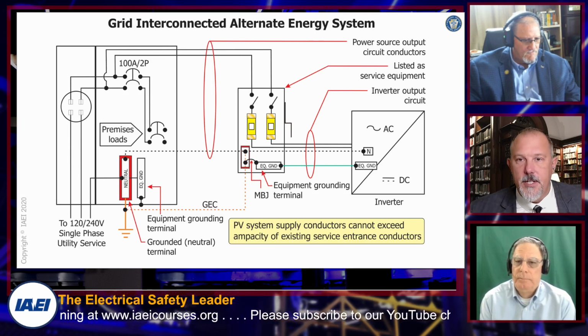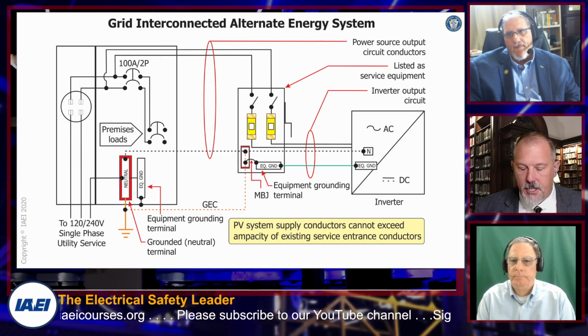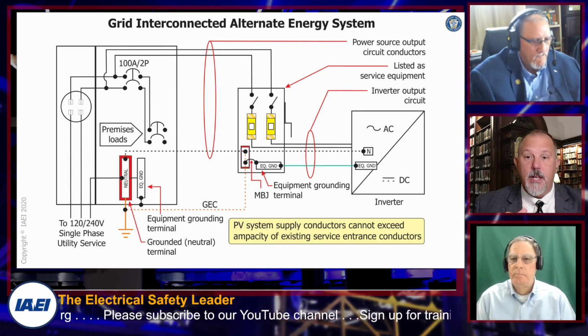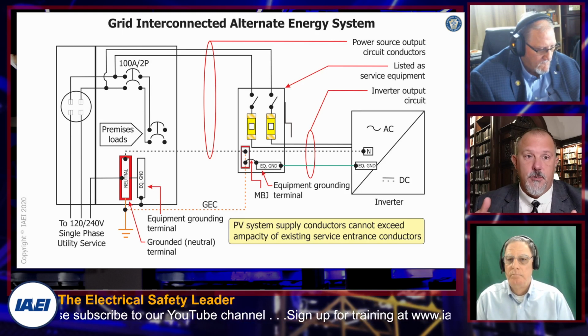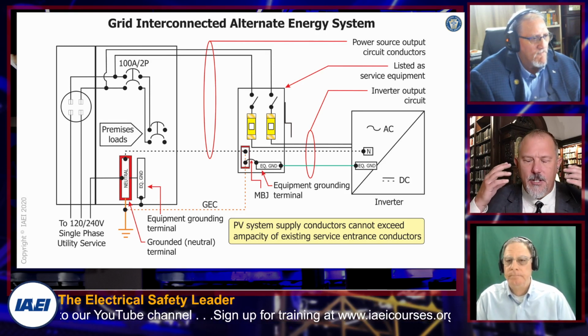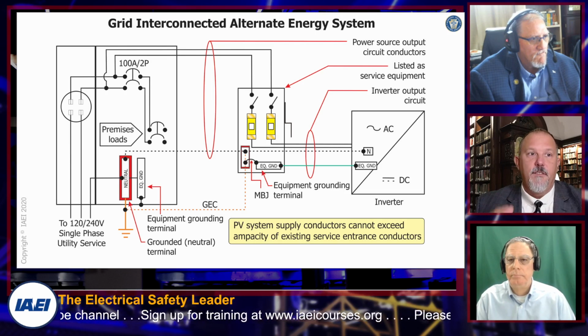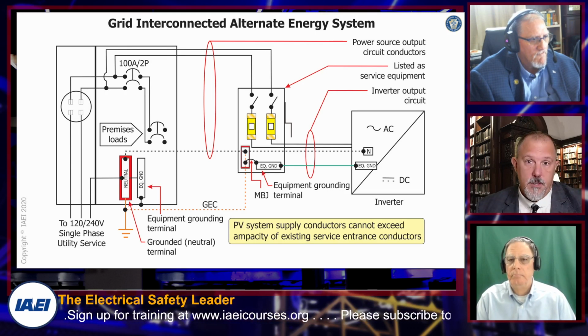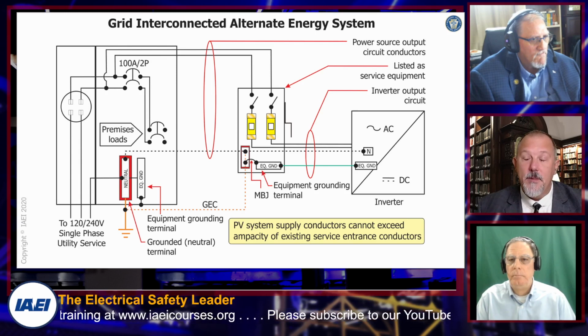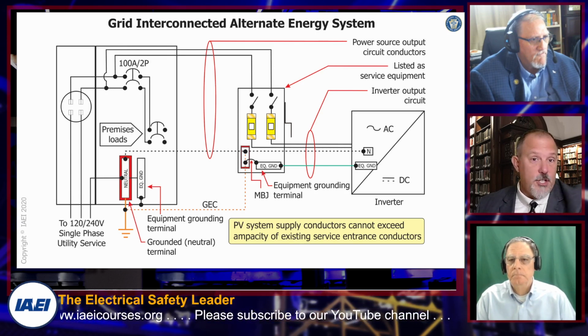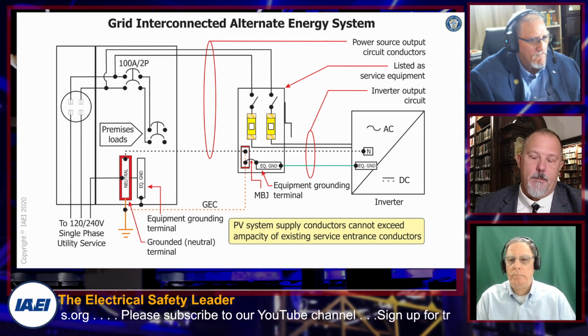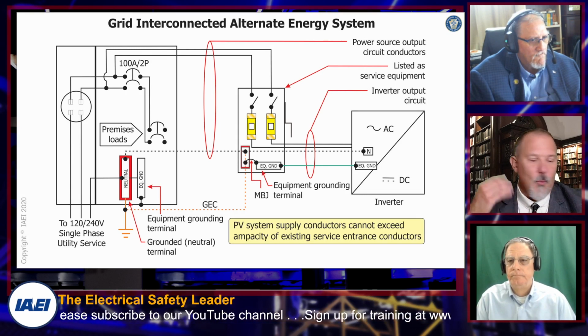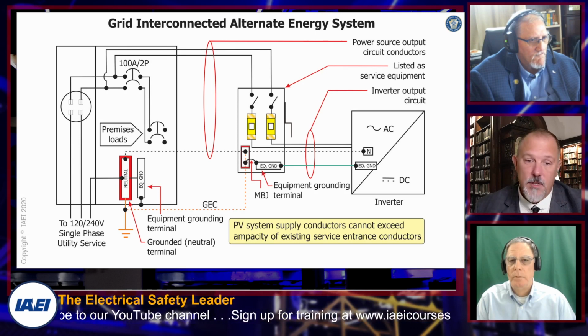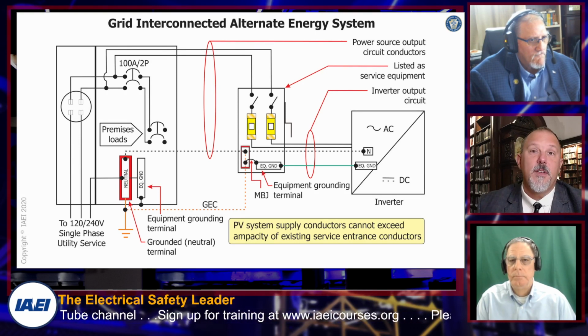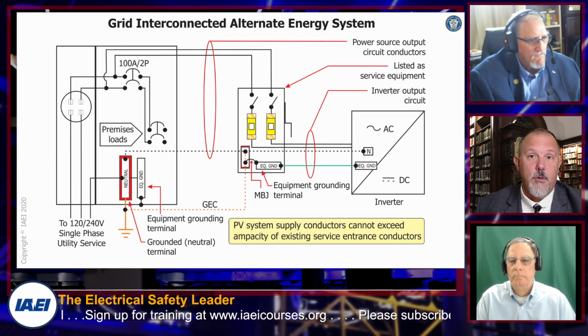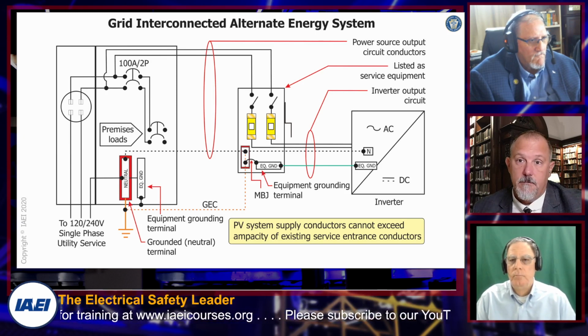We were talking series ratings with an engineer, trying to help them understand that when dealing with series ratings, you're dealing with motor contribution, and comprehending during a fault condition the flow of current within a power system and how it impacts the performance of overcurrent devices, not just in this but in many other NEC applications. So the one line diagram and these diagrams are really critically important to help convey and help people understand the flow of current in normal and abnormal situations in the system.